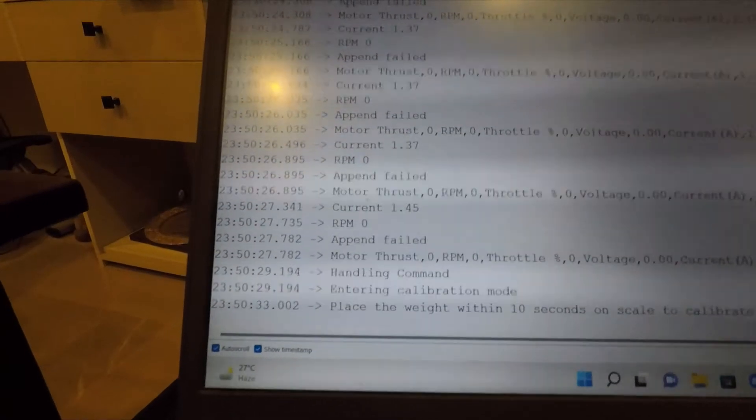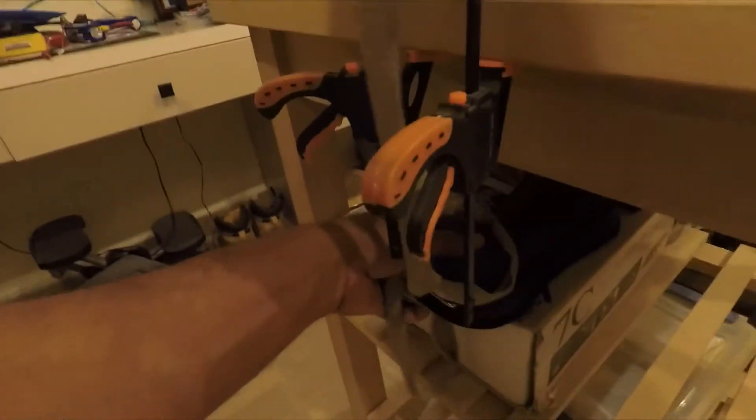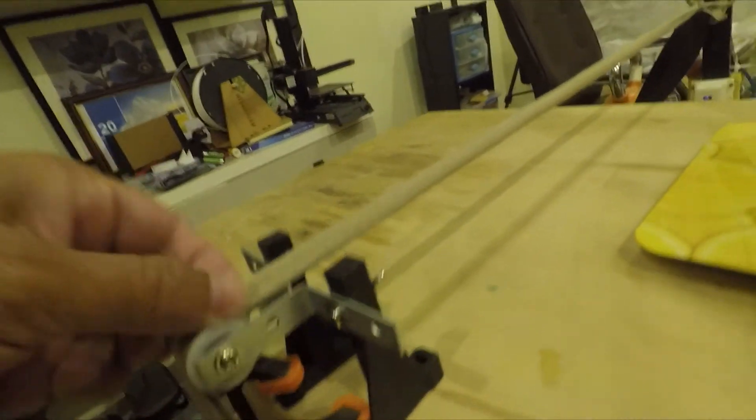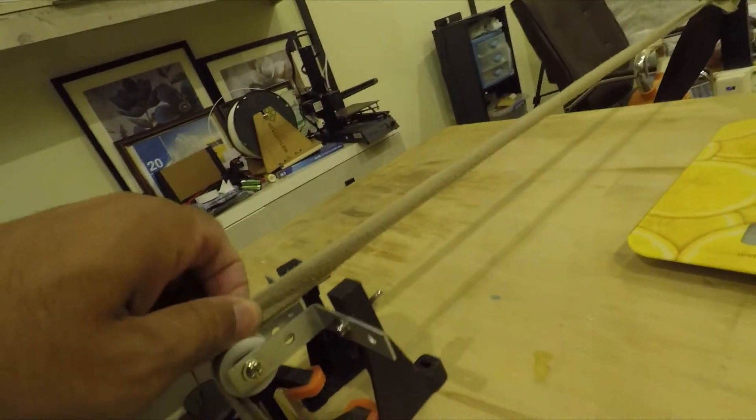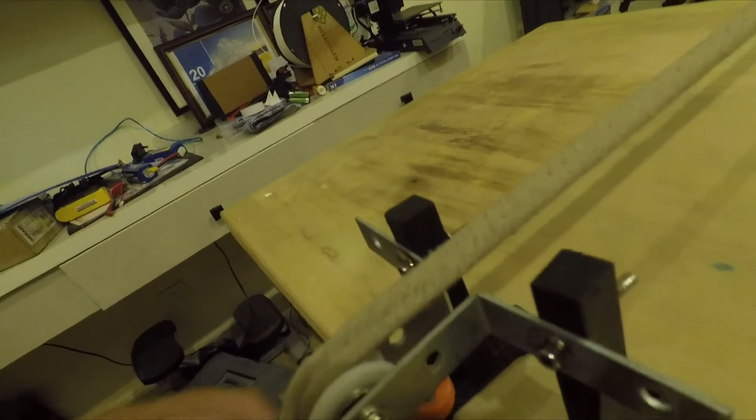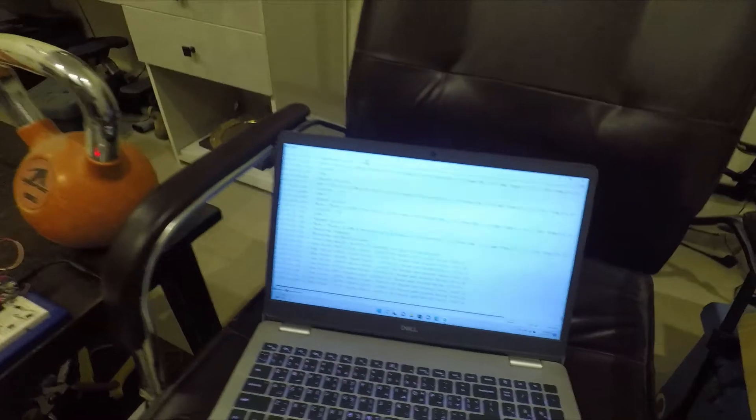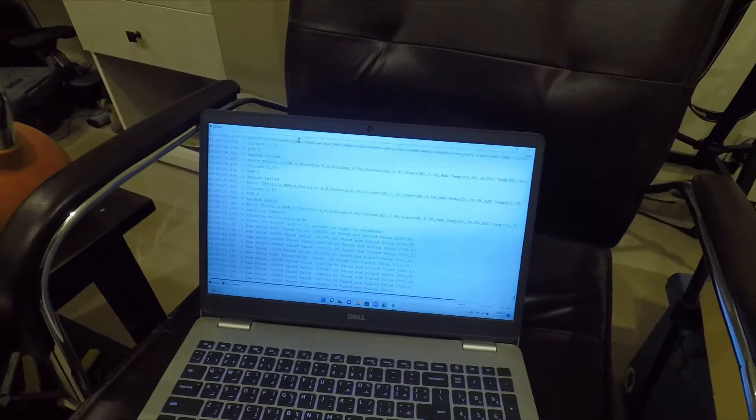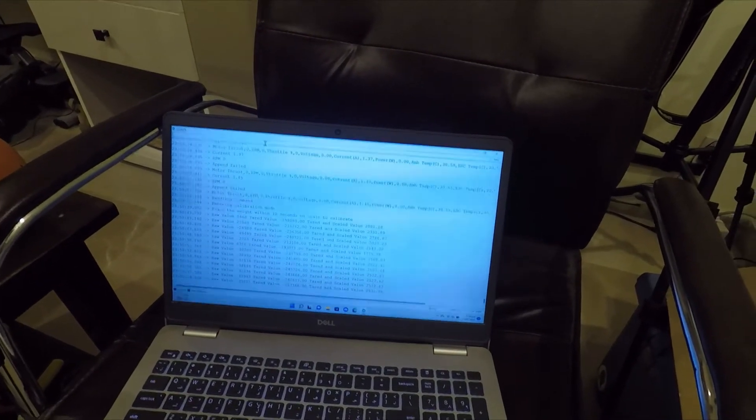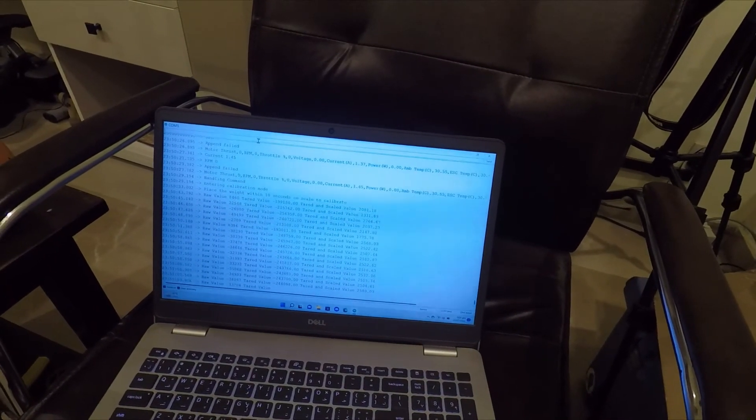Command entered. It will give me 10 seconds. Here we go, system's entering calibration mode. I will apply 2000 grams of weight. Make sure that it's fully applied, and if properly done, the system should take this as a calibration value and it will start showing on the screen the actual value measured, which should be your calibration value. If it doesn't work properly, you can repeat it as many times as you want.